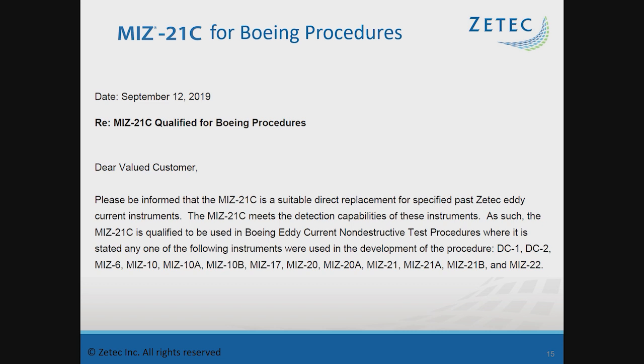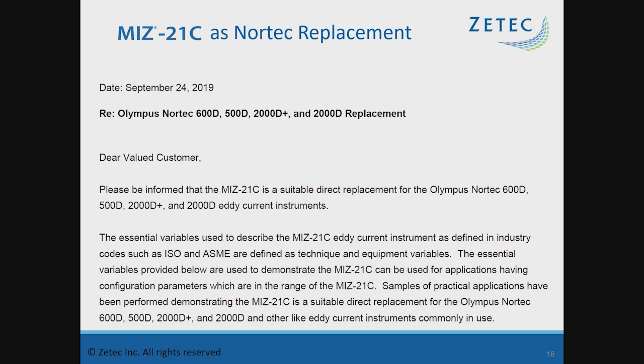The MIZ-21C also applies to Boeing procedures where it was used with previous MIZ instruments or DC instruments. There is a full list of MIZ instruments — MIZ-6, 10, 17, the 20 series, and the 21 and 22 series — that were written into or used to develop Boeing procedures that the MIZ-21C is equivalent to and qualified to replace. Zetec also performed a comparison to the Nortec series of instruments to confirm it is a suitable direct replacement for the Nortec 600D, 500D, 2000D+, and 2000D, examining the same technique and equipment variables.